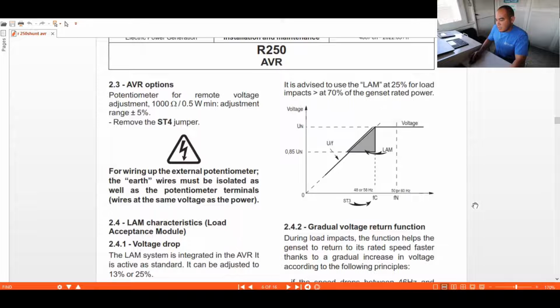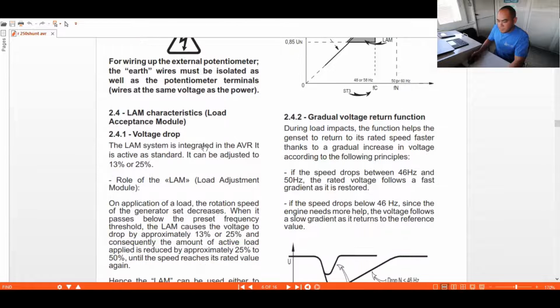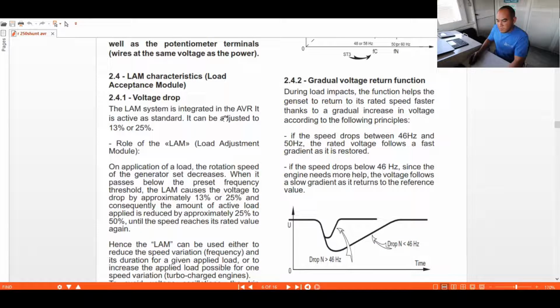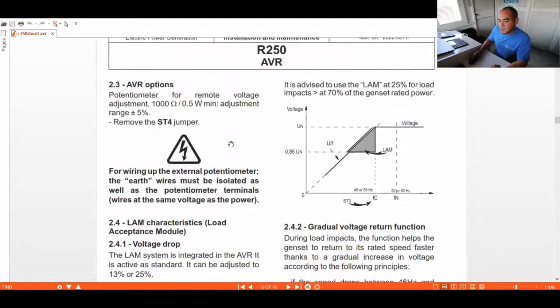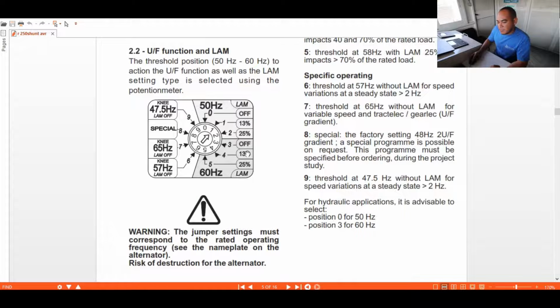Okay, so back down here. As you can see, this is the graph for your LAM. It is advised to use the LAM 25% impact to 70% of genset rated power. So you have the voltage and your frequency. This is your LAM position. This is your 48 and 58 hertz, so it's 50, 60, corresponding to 50 and 60. So that is your graph at this point. Here the LAM system is integrated as the AVR is active as standard. It can be adjusted from 13 to 25%. As I told you, 13 to 25%, 50 or 60 you can apply.